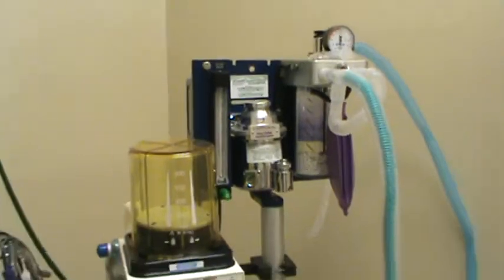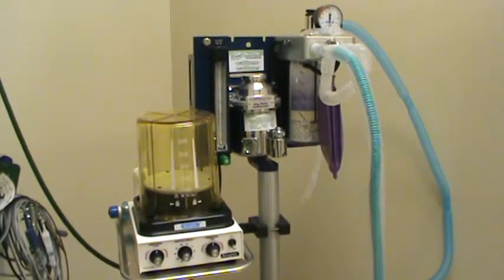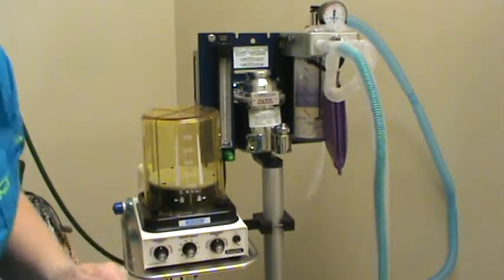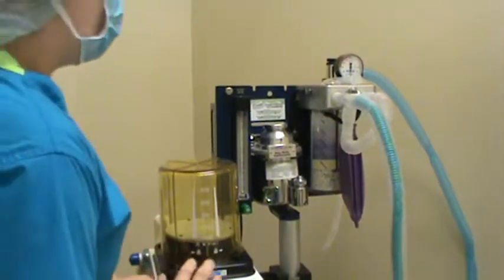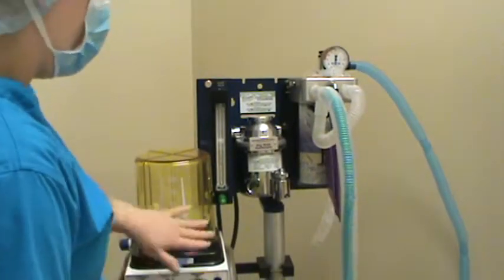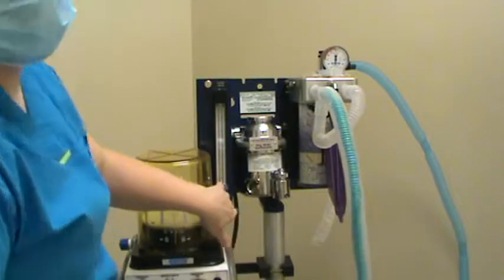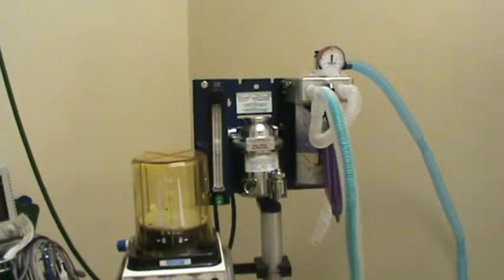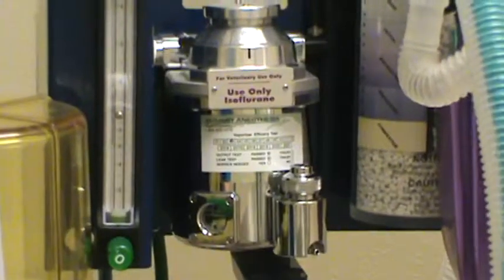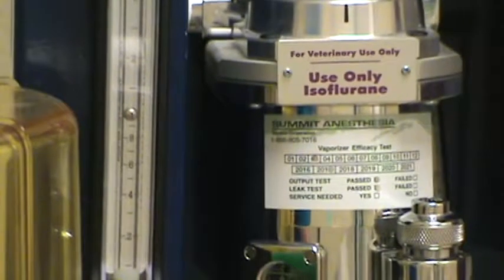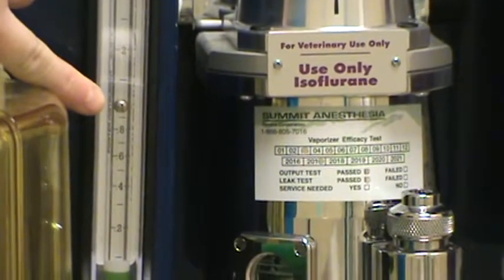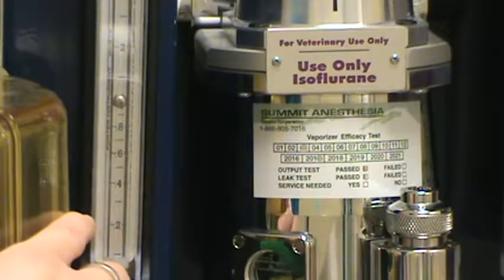Here we are at our anesthetic machine. First thing I'm going to do is verify that the oxygen is working. I'm going to turn the flow meter here. The flow meter is on and right here at about one, so we have oxygen flowing and that's great. I'm going to turn that off and zoom back out.